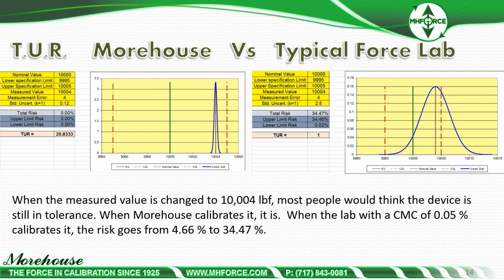If we change the measured value to 10,004, one lab can still say it's in and one cannot. So if you're looking to have a lab make that statement of conformance or compliance, they change that terminology as well, depending on it, you want your device to be in tolerance. A lot of labs, when they account for that decision rule or take measurement risk into account, are not going to be able to give you the pass. If you're looking at a device that's 0.1%, and their CMCs are at 0.05, they're going to have less of a window.